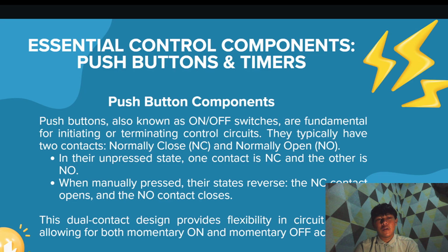Essential control components: push button and timer. Push button components. Push buttons, also known as on or off switches, are fundamental for initiating or terminating control circuits. They typically have two contacts, normally closed and normally open. In their unpressed state, one contact is NC and the other is NO. When manually pressed, their state reverses. The NC contact opens and the NO contact closes. This dual contact design provides flexibility in circuit design, allowing for both momentary on and momentary off action.